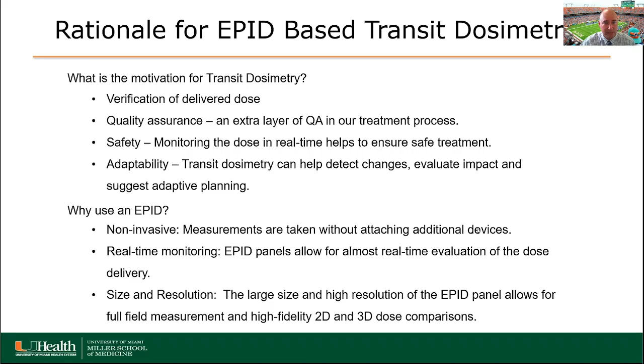So a quick review of the different flavors of transit dosimetry using an EPID, starting from the least complicated to the most complicated. 0D is where we utilize the EPID to make a point measurement in the patient. So you will capture the exiting dose from the patient, and then you will reconstruct that dose back at a single point. That's typically done at isocenter, but can also be done at other locations. It is then not overly complicated. It can be a very efficient tool for tracking basic fractional dose delivered. I think this satisfies some of the requirements that maybe our European colleagues have for tracking dose for each fraction.